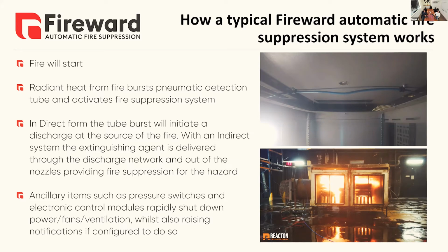However, with indirect, the system is delivered through a discharge network after that tube has burst, as mentioned by Ed earlier. And then the ancillary items, which we touched on, such as pressure switches and so on, can control electronic modules. They can shut down power, fans, ventilation, and also it could be connected to your building management system or control panels, which can then do proper audio and visual alarms for people as well.